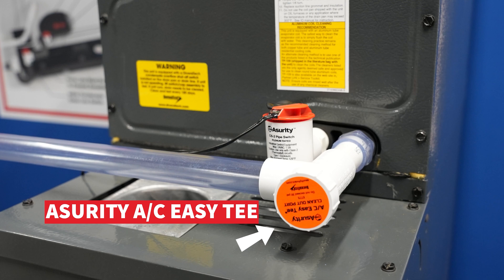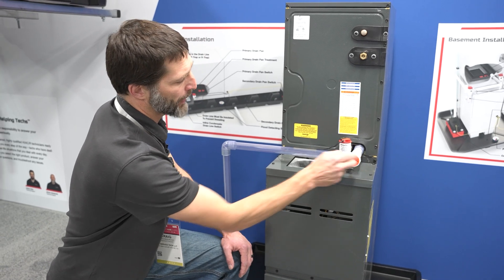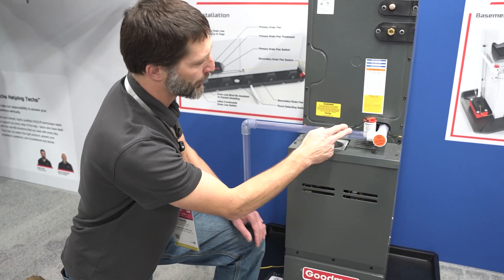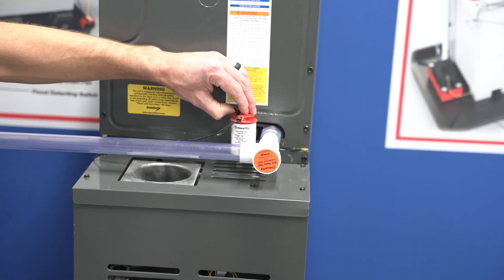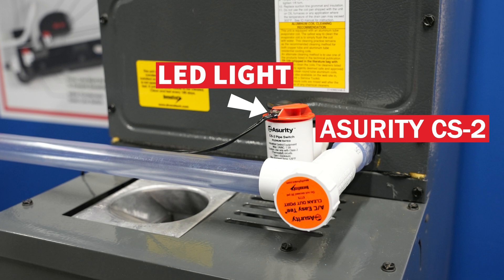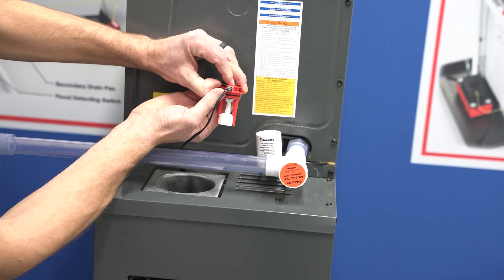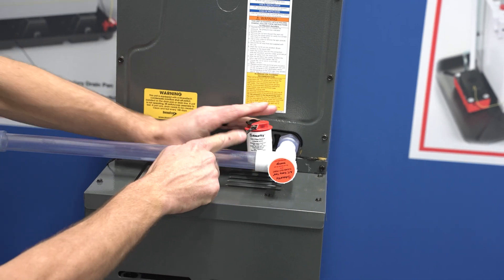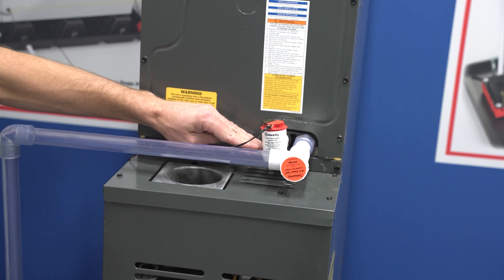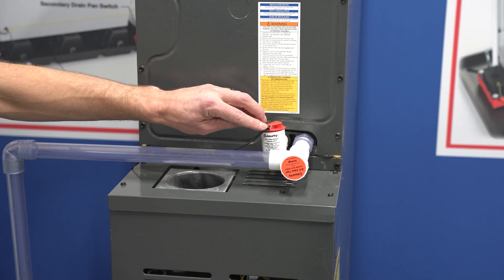Here we have the Asurity A/C Easy Tee. It's a very quick, easy clean-out section for your piping, and you have clear piping so you can see if you're going to have any problems. There's a test function by being able to pull this up, and there's an LED light. If I pull this up, we're going to be pulling the float up — it's going to break the electrical switch if the water level rises within the switch, tripping that float inside. What's nice about this is there is that LED light.